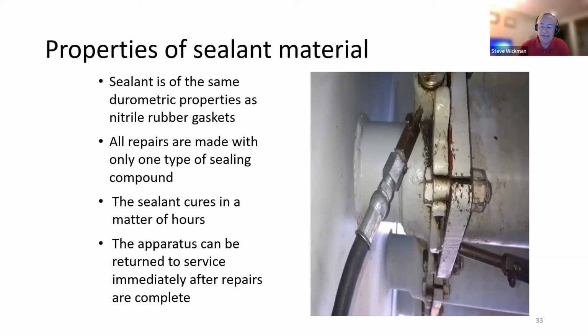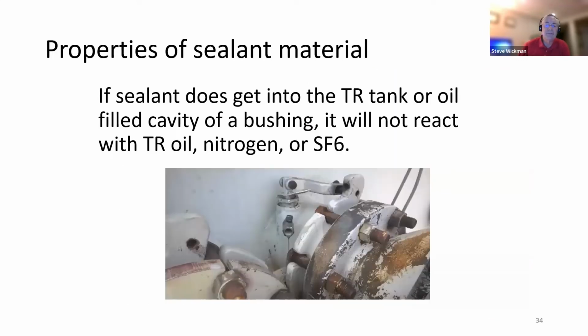Again, like I say, we like to leave it out overnight to make sure everything's cured up and it's all good. Now, if the sealant does migrate into the transformer tank or oil-filled cavity of a bushing, it will not react adversely with transformer oil, nitrogen, or SF6, the fluids and gases that are commonly used in electric apparatus these days.